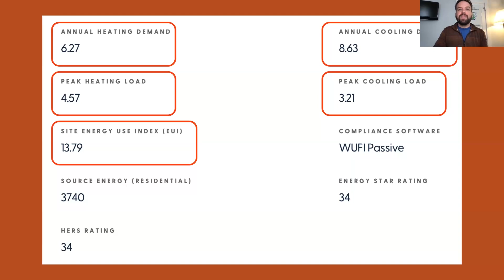Some interesting components in this house - we actually needed to do a makeup air system. Anytime you've got a range hood pulling more than 400 CFM in any kind of house, you need makeup air. For passive houses, the pressure differentials can be pretty significant, so there's some massaging to be done about whether makeup air systems make sense, and when you're in a cold climate, whether you need to preheat that, what the energy costs are, et cetera.